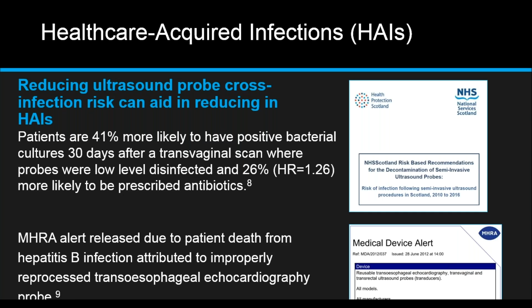Now, more than 80% of probe handles, that is, not the part of the probe that's actually inserted into the body, but where the user is holding it, are not disinfected and have residual pathogens. And again, that's not surprising. When the user handles and moves the probe, they would carry pathogens from the area that touched the mucous membrane of the patient onto the handle. And it goes without saying that the colon, the esophagus, and the vagina are not sterile and, in fact, normally have logs of organisms present. Now, one certainly should use and can use condoms over the probe, but up to 10% of condoms and barrier sheaths leak. Therefore, their use does not replace the need for high-level disinfection.